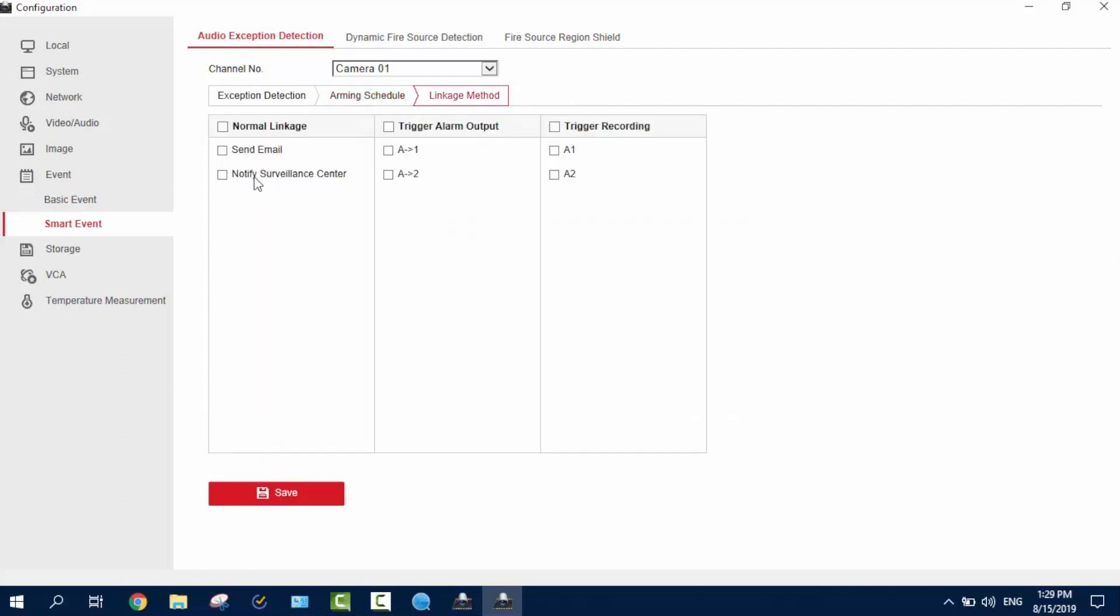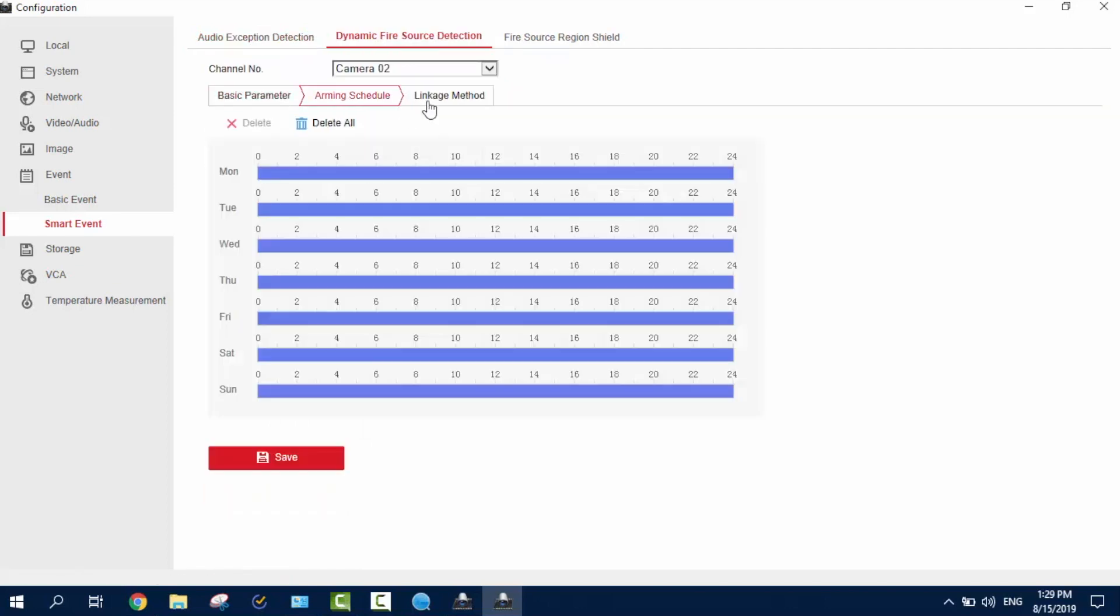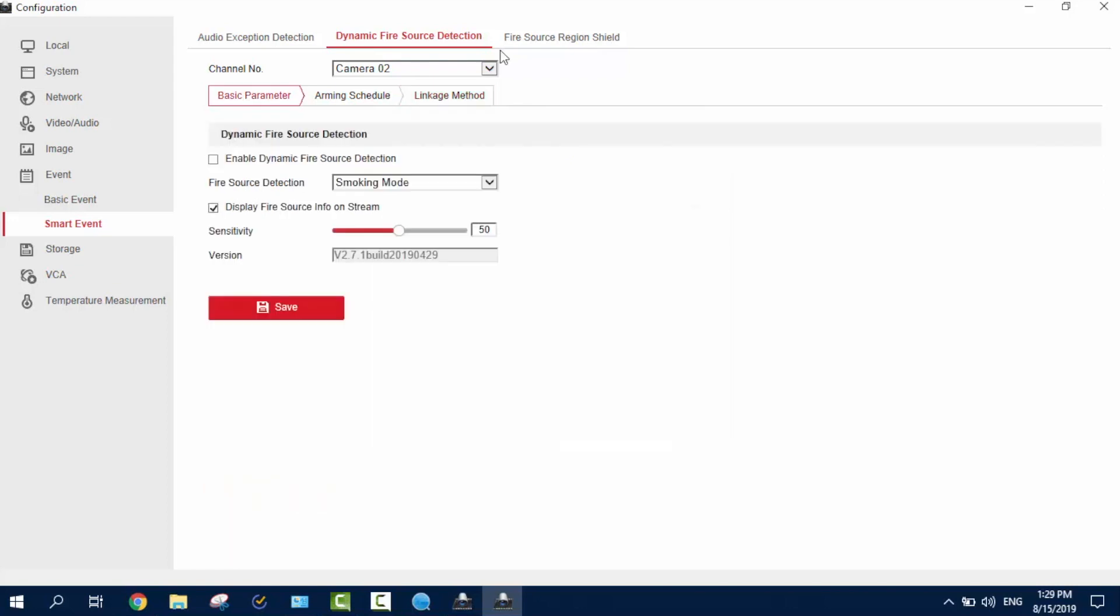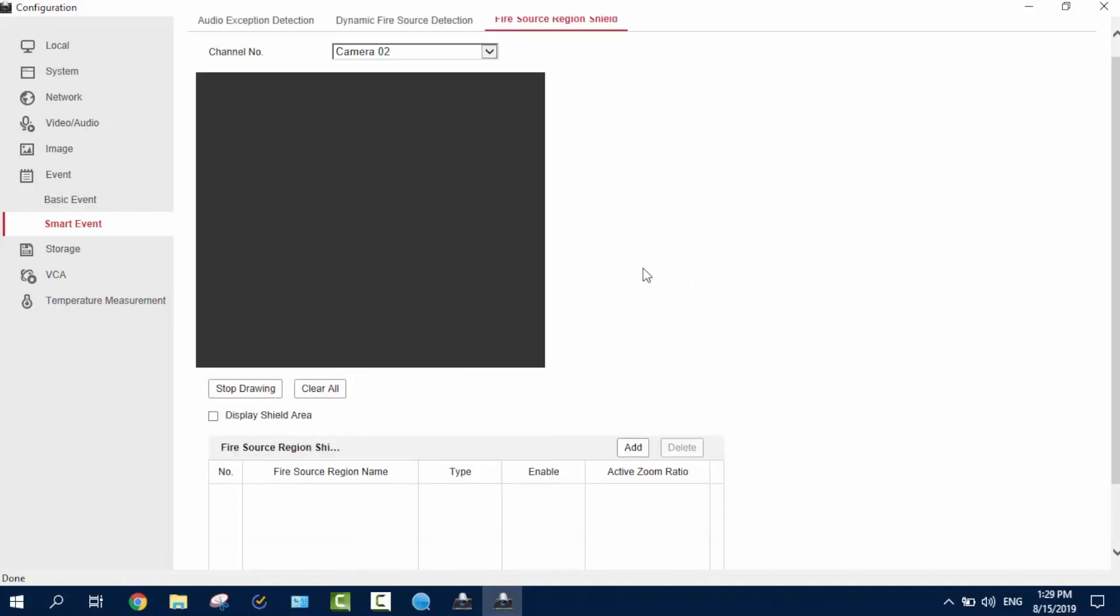And of course, a notify surveillance center. Dynamic fire source detection. Of course, we can turn it on here. And fire source region shield. I mean, if you know something will be really warm, you just draw an area in here where you know will be warm, and enable, and you get saved. So, it will, so you won't be notified if something warm happens here, but it will be notified if something warm happens here.